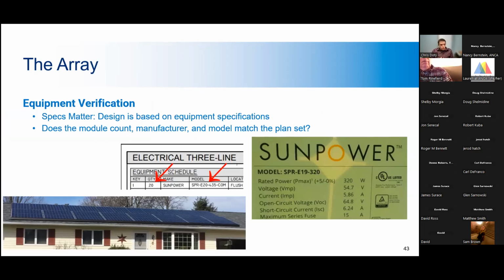More on the array. What you want to do is compare the electrical diagram provided by the contractor and the equipment nameplate information that's found on site. As you can see, here we have the information from the electrical diagram that was submitted with the permit, and here we have the nameplate information for the solar panels. You can see their different model numbers, and you want to make sure that they do match. This is very important because all of the other equipment in the design is based on the solar array. So if you have different wattage panels, or different panels with different amperage or even different voltage, it may not be compatible with the rest of the equipment in the design, and that may cause problems down the line.